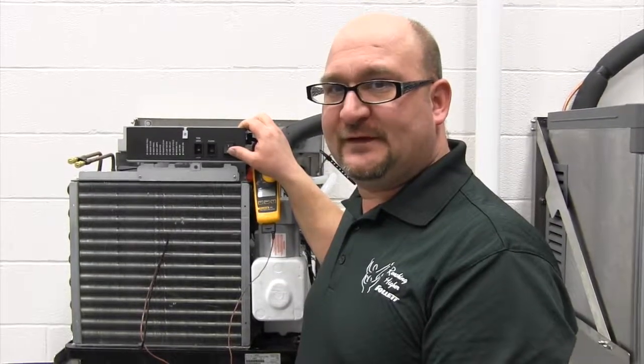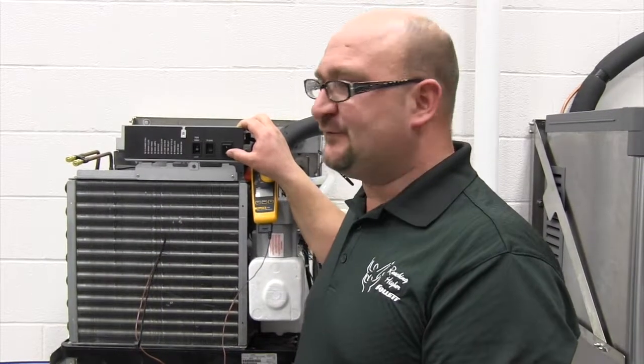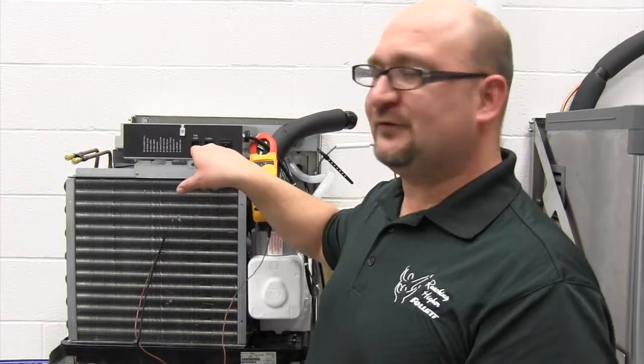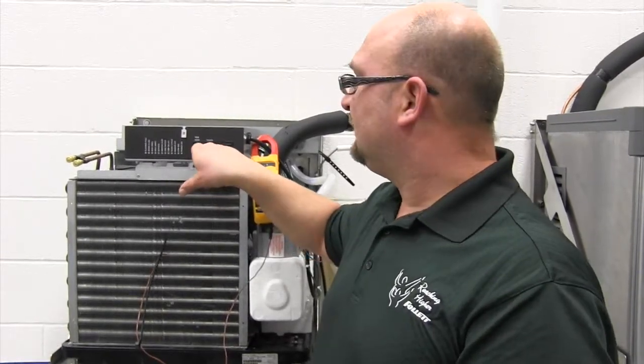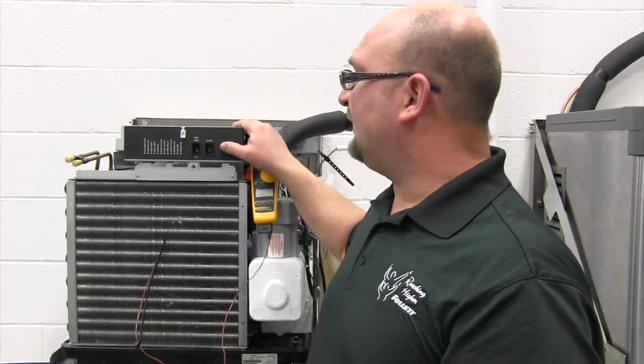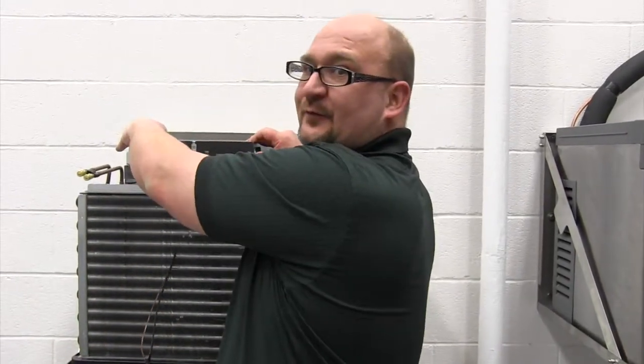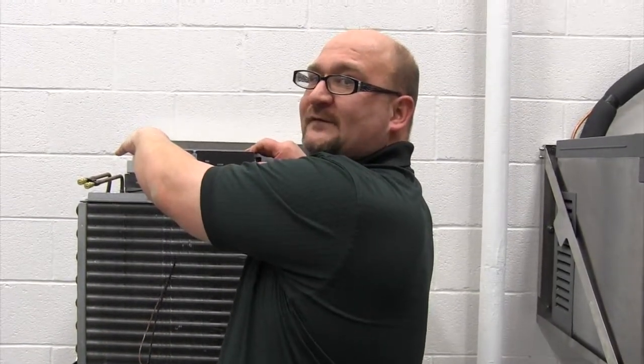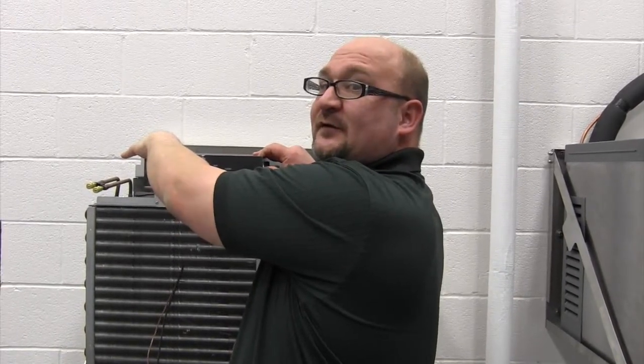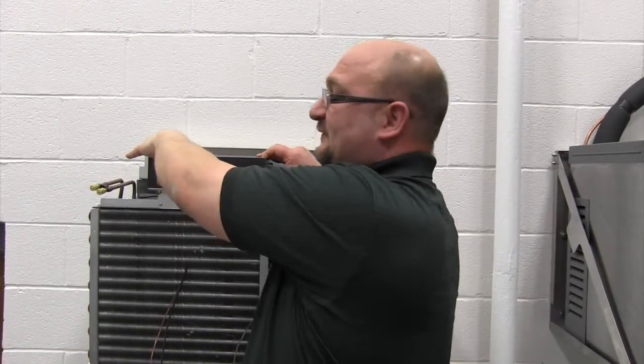We let the ice machine run for about 15 minutes, then we're going to shut the ice machine off. We're going to change our TDS switch to low, turn the pilot back on, and hit the reset button located on the circuit board. That's going to reset the circuit board for the flush timing so that the unit doesn't flush during our production test.